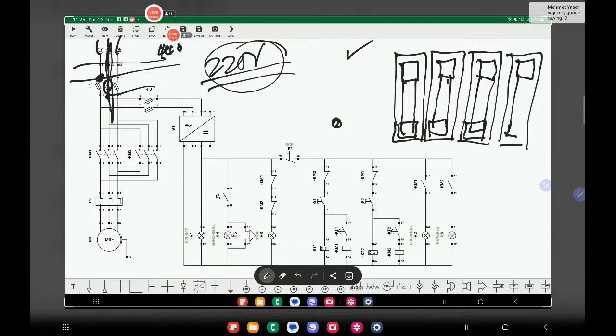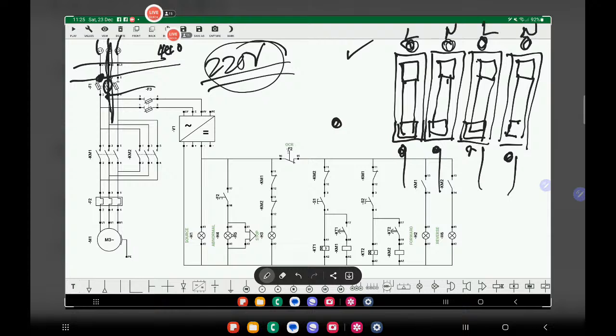So you will know which one is busted by just measuring your input and output voltage. Let's say both of these are just 220 volts. Now this is L and N, L and N, and then this would be your output. So if I want to know if there is a busted fuse, I'll measure line and neutral onto the first line, these two pair, so for sure they are paired, then the L and N, so I should be having 220 for both, no?